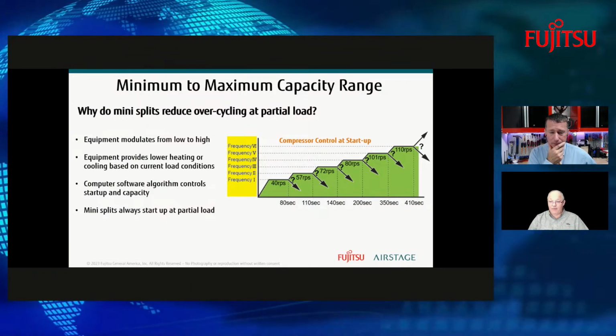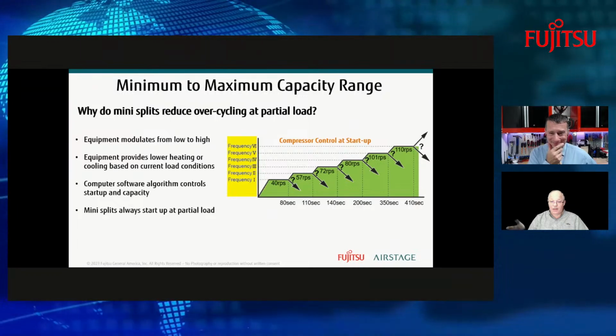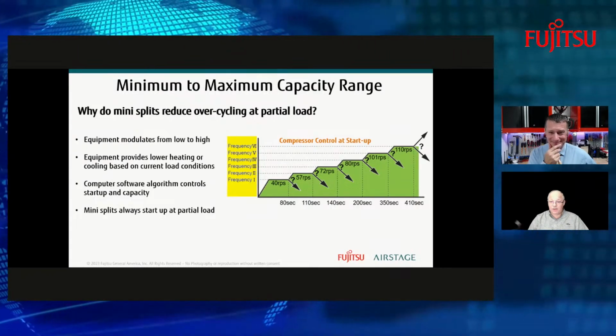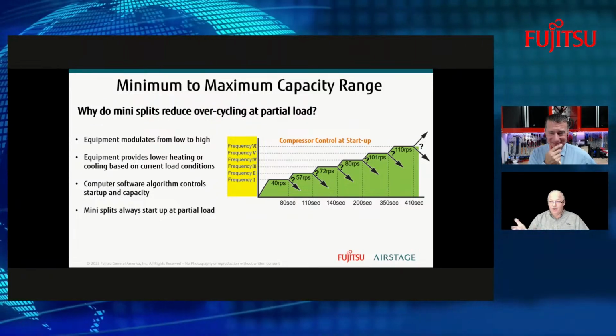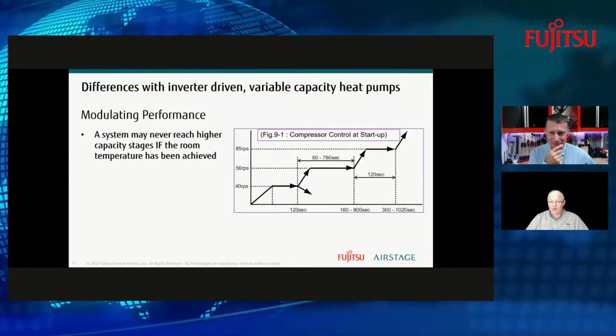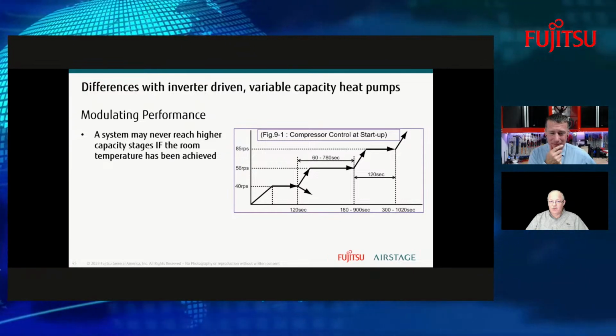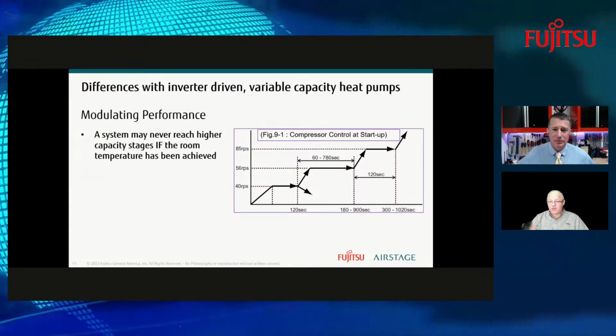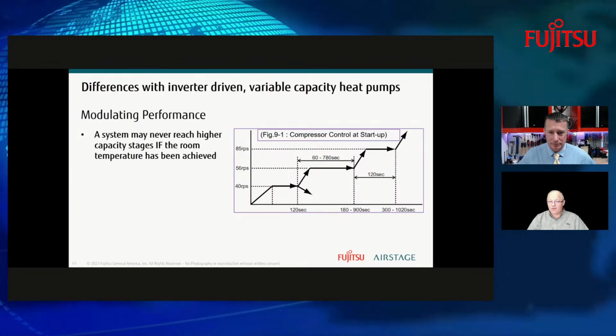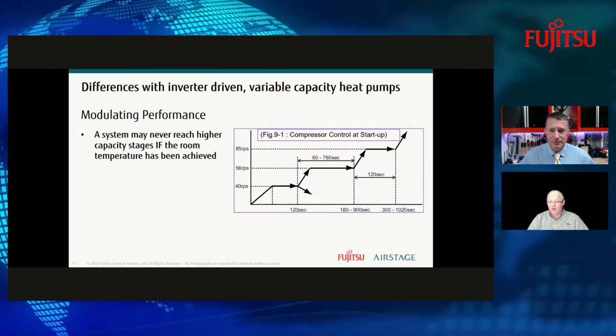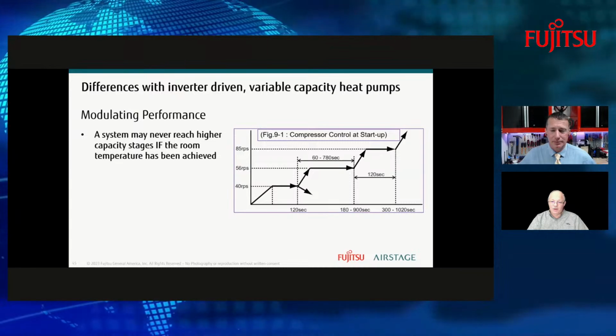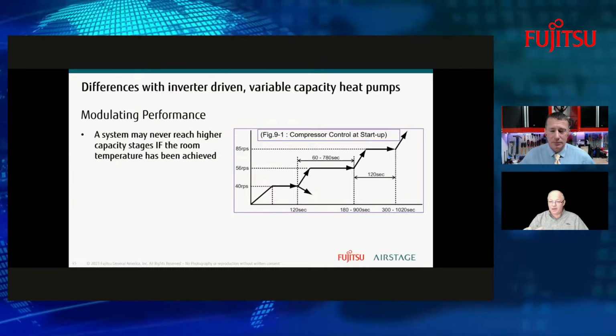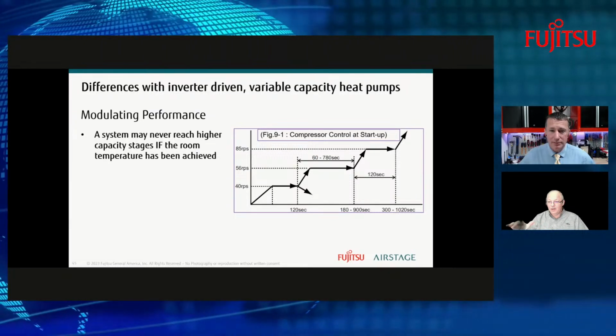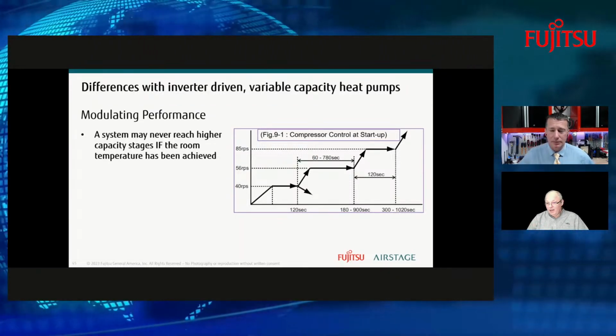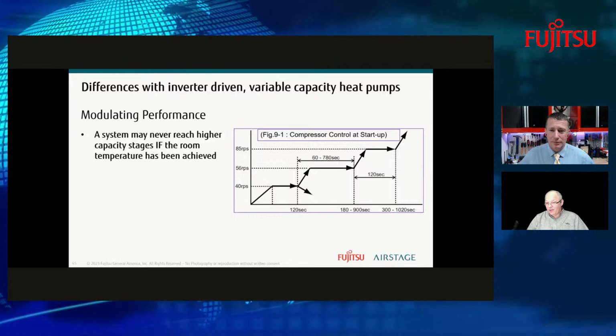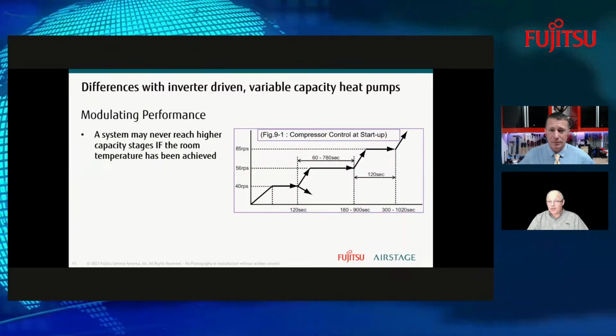It's nice to have that fast Corvette, but you're only going 1 block down the road. Why do you need to spin the wheels? That's why we don't need to modulate way up to high on a mild day. We don't need to go that fast. So this system may never reach the higher stages if the room temperature has been achieved. That's the beauty of it on mild days. Now, if it's really super hot outside, you're still going to ramp up through the sequence. But if you have a day where it rains, the temperatures are going to drop, and you're going to be modulating even lower.